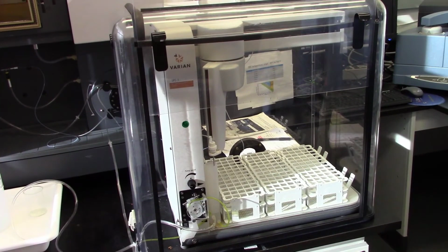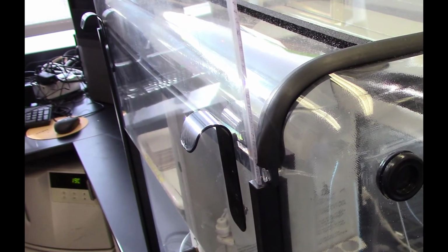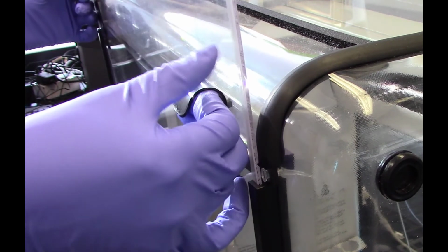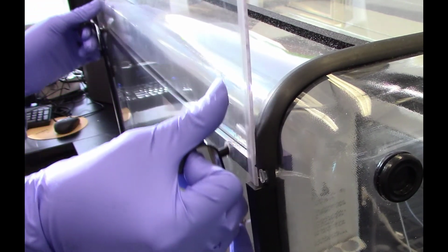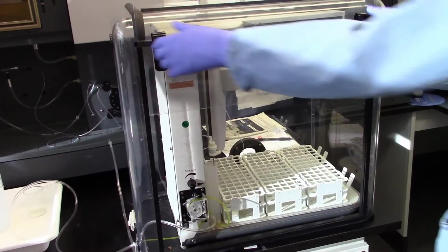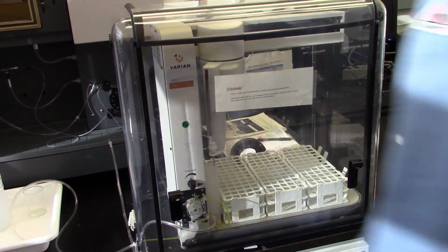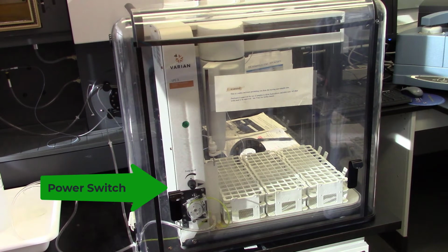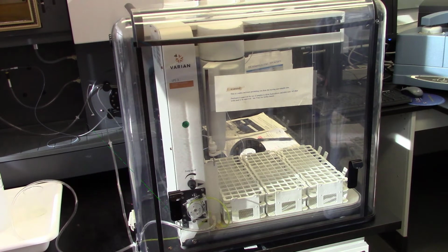Now let's look at the autosampler. If it is already on, you will see a green light on the top of the instrument. If it's off, close the safety cabinet door by pressing your thumb above the tab and gently sliding it down. You're required to have this door lowered anytime the robotics are moving. Then flip the switch on the back lower left under the power cord to turn on the system. Wait until the autosampler arm has stopped moving before you start the software. If it hasn't, the autosampler will not connect to the computer and you'll need to restart it.